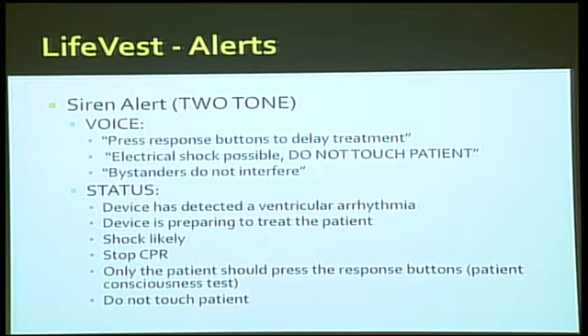Two-tone siren alert with a voice saying press response buttons to delay treatment, or there's a vibration, or it'll say electric shock possible, don't touch patient, or bystanders do not interfere. It'll say any of those things. That means it's detected a ventricular arrhythmia and it's going to shock the patient. So stop CPR at that time, stand back. If the patient's alert and awake, they can press the response button to stop it.